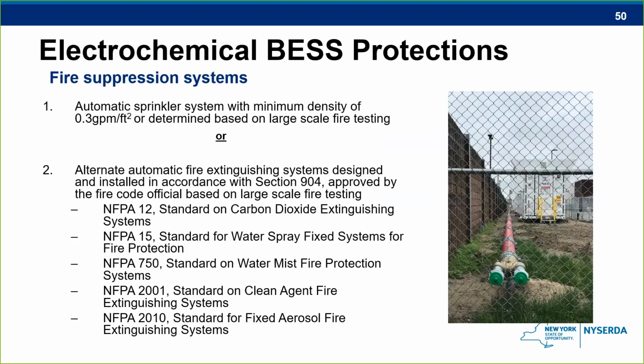Fire suppression systems. So although the code calls out this water density, which is 0.3 gallons per minute per square foot, it may be a challenge to get that much water to the upper floors of a high-rise or in an area that does not have good water pressure. In outdoor locations, some AHJs are using a dry pipe that the fire department pumper would be supplying the water to. And this is used so that automatic water suppression systems don't accidentally freeze or malfunction and cause the water to flow on a system that perhaps had no problem. So there are some options here. And on top of that, you'll see that instead of water, you can use other approved non-water extinguishing methods that are listed out on number 2 on this slide.